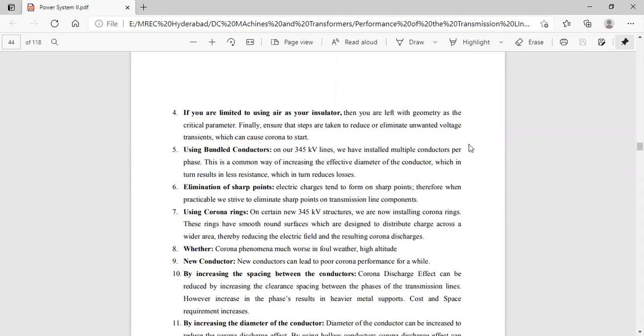The fourth one is, if you are limited to using air as your insulator, then you are left with geometry as the critical parameter. Finally, ensure that steps are taken to reduce or eliminate unwanted voltage transients, which can cause corona to start. The fifth one is using bundled conductors. On our 345 kilovolt line, we have installed multiple conductors per phase. This is a common way of increasing the effective diameter of the conductor, which in turn results in less resistance, which in turn reduces losses. The sixth one, elimination of sharp points.